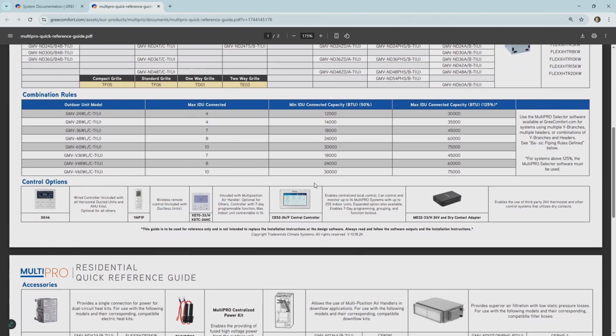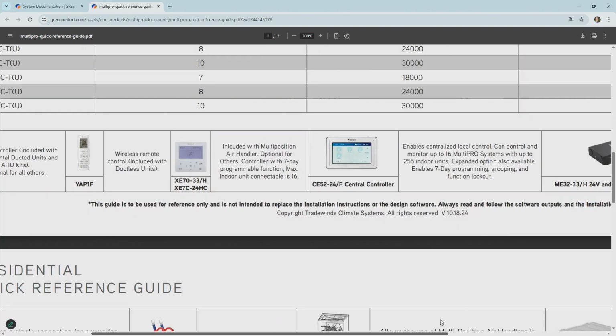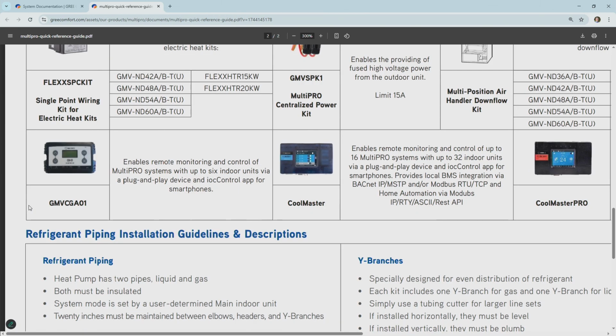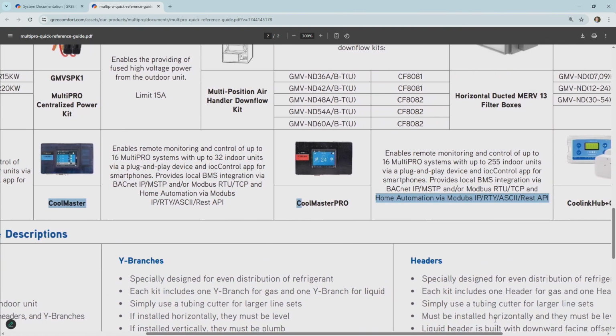come down a little bit, right there. You see that CE52-24F central controller. That's what you'd want to use in that instance. Or the other option you would have, that GMV CGA01 is cool automation control. It will do up to 6 indoor units. You can go to the Cool Master, which will do up to 32 indoor units, and Cool Master Pro, which does up to 255 indoor units. Now, with that, you'll be able to control it with your phone. You can go to a tablet. You can do it on a computer. Doesn't matter. And that would give you more of a central location to control all your units without having to run all over the house.